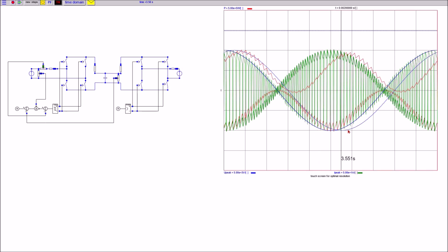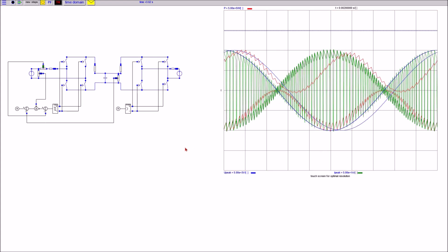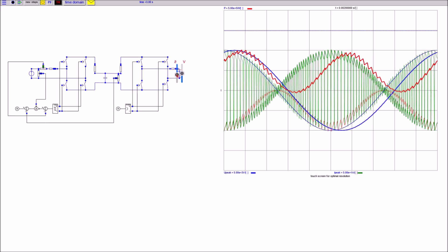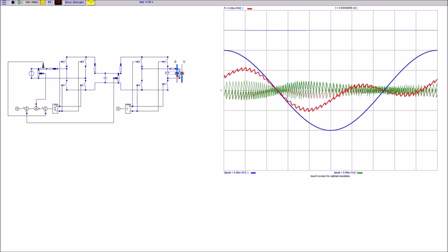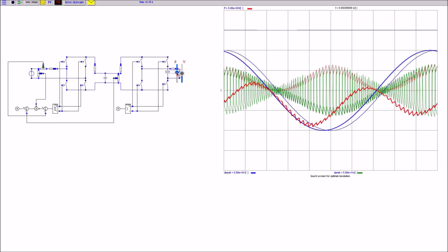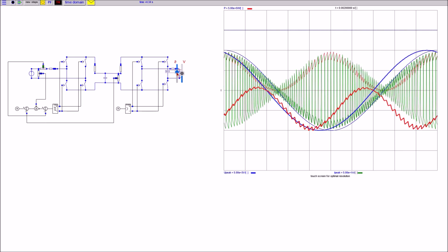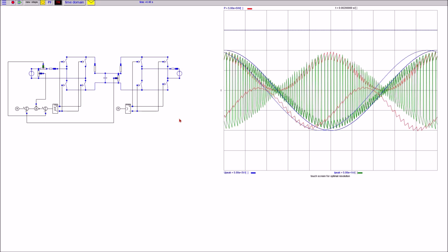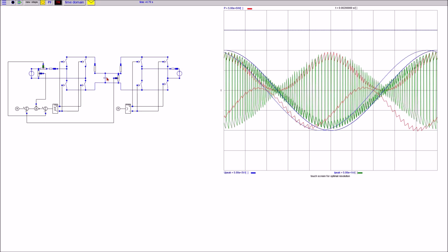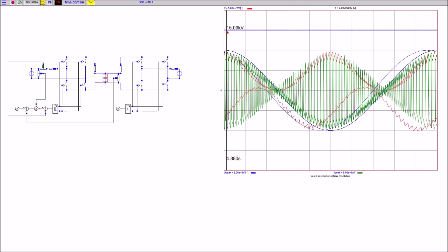The converter on the left side is controlled by means of a current modulator as explained previously. The current modulation controls the DC voltage and compares it to the reference. A smaller DC voltage compared to the reference will immediately be compensated by a power flow from the left AC grid to the DC side and vice versa. Given the static reference signal for the right converter, it is only the AC power source on the right side which governs the power flow.